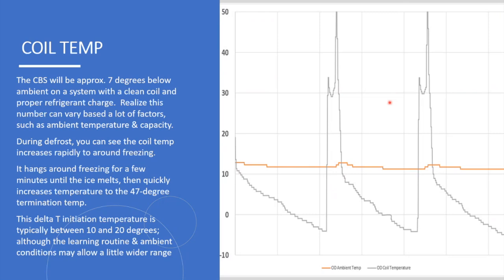It's going to aim for a defrost cycle of 4 minutes, and has an adaptive learning algorithm. So if this defrost process takes longer than 4 minutes, it's going to tighten up this delta. If it takes less than 4 minutes, it's going to let it go to a larger delta before it initiates a defrost.